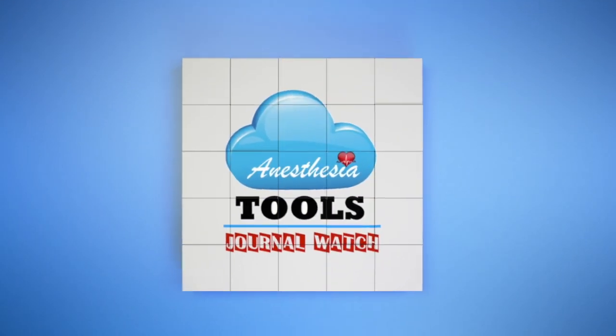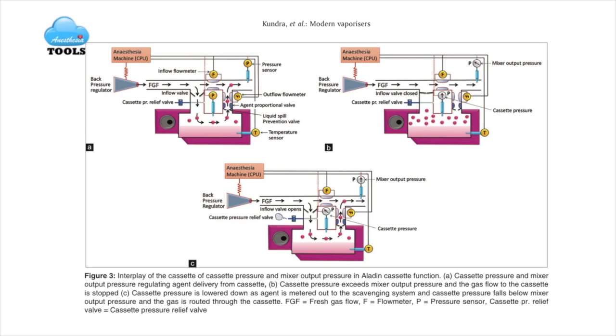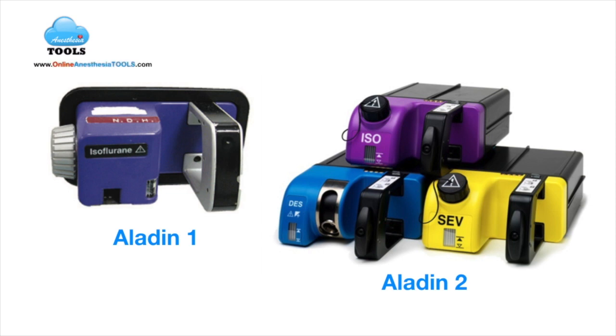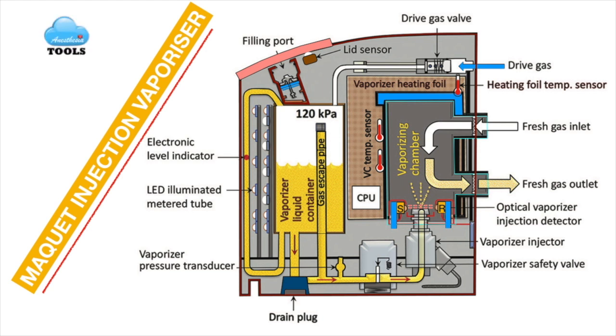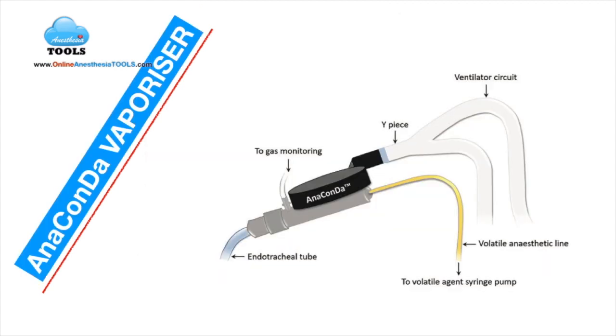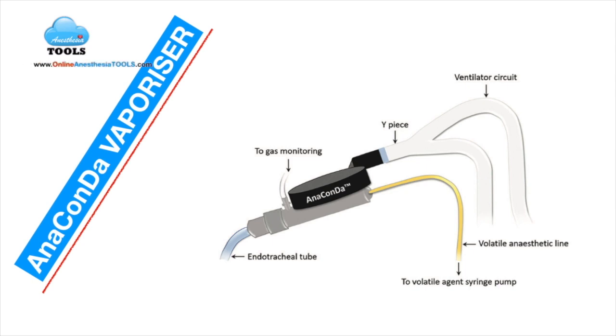The article also features further schematic explanation of the interplay of cassette pressure and mixer output pressure. The differences between Aladin 1 and 2 vaporizers are also discussed. The latter part of the article deals with two more important devices: the first is the Maquet injection vaporizer, and the latest addition is the Anaconda — an anesthetic conserving device that is a miniature anesthetic vaporizer and HME (heat and moisture exchanger) filter combined together, meant mainly for sedation in the ICU and outside operating rooms.